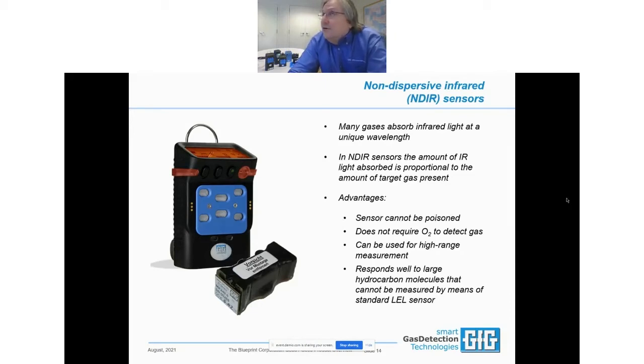So where do you run into pure methane? Nowhere, not very often. If you have even something like natural gas, 10% of the natural gas comes from other stuff, like propane and ethane and other unsaturated hydrocarbons, especially if it's raw natural gas. So some of these other materials have almost no response. Some of them have a response that is wildly greater than the response to methane. If you're trying to come up with a quantified number, good luck. What you have with those micro-miniaturized sensors is a yes-no indicator of a few gases.